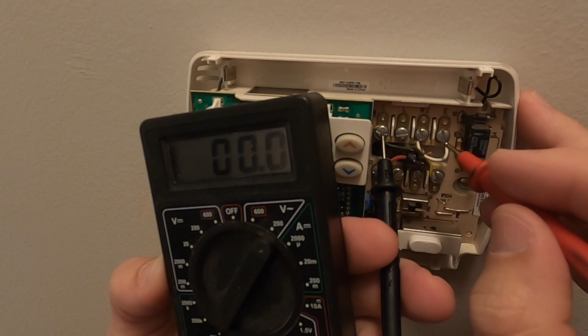Even though we're checking it here at the thermostat, it does not mean the thermostat is the source of that 24 volts. We have to go downstairs, find where the white wires connect, disconnect them, and then test them individually to see if the electricity is coming from the thermostat, coming from the outside unit, the condenser unit, or inside at the air handler. And then we'll know which one to deal with.